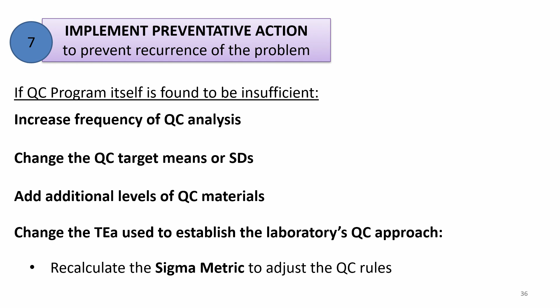So in conclusion, we've discussed the steps to recover from an out-of-control event. This is a systematic process. Phase 1, detect the error, immediately stop patient testing, investigate and identify the root cause of the problem, implement corrective action. That's not the end of the process. You then move to phase 2, where you're evaluating the impact of the problem on patient results using allowable total error, mitigate patient harm by calling providers and issuing corrective reports, and finally, implementing preventative action to prevent the problem from reoccurring.